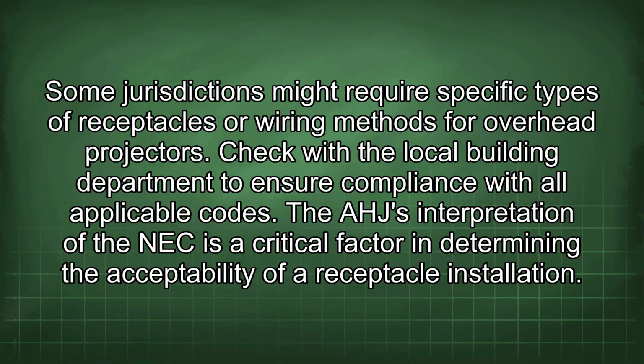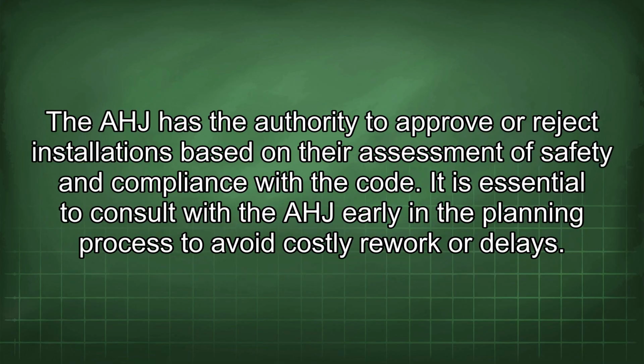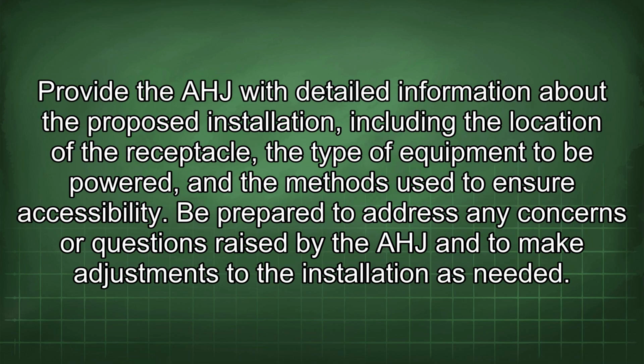The AHJ's interpretation of the NEC is a critical factor in determining the acceptability of a receptacle installation. The AHJ has the authority to approve or reject installations based on their assessment of safety and compliance with the code. It is essential to consult with the AHJ early in the planning process to avoid costly rework or delays. Provide the AHJ with detailed information about the proposed installation, including the location of the receptacle, the type of equipment to be powered, and the methods used to ensure accessibility. Be prepared to address any concerns or questions raised by the AHJ and to make adjustments to the installation as needed.